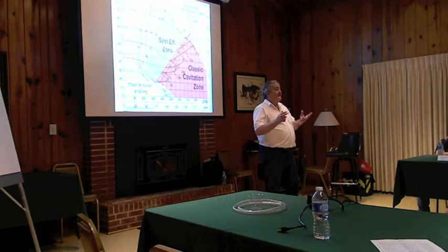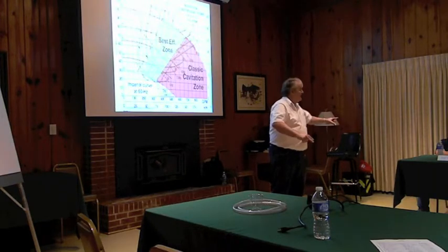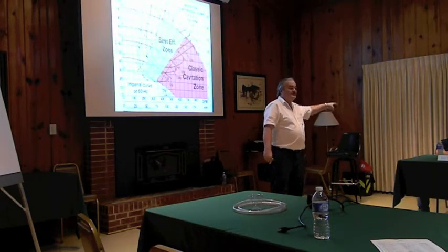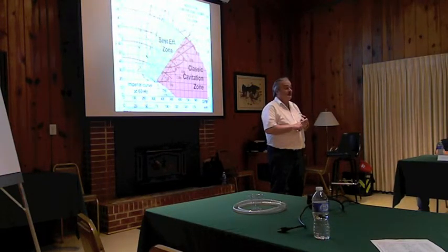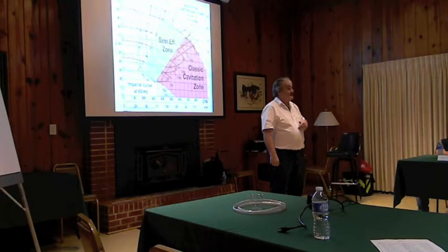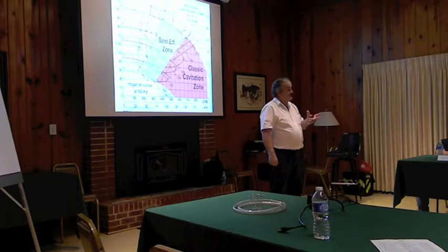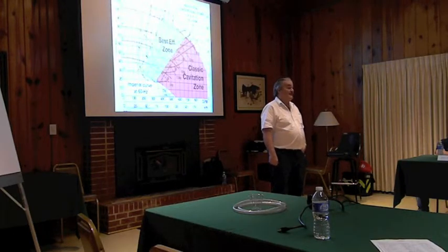So what have we considered so far? Process or sales demands that we run the pump at 900 gallons a minute — the pump goes out there on the curve. If it tears up the bearings and seal by tomorrow morning, who should pay for the repair? Is that a maintenance problem, or a production cost, a cost of sales? These arguments make people pay attention. The natural tendency is to say somebody screwed up the mechanical seal during installation — but maybe that's not why the seal failed.